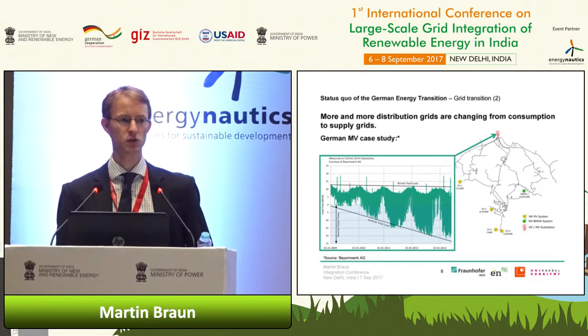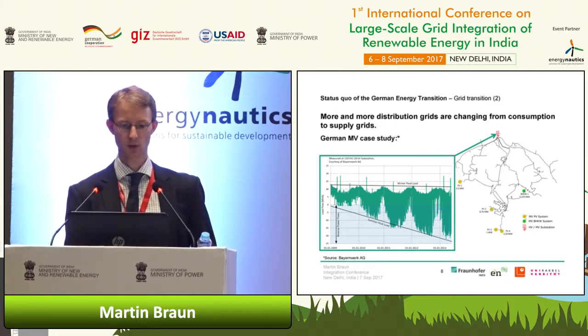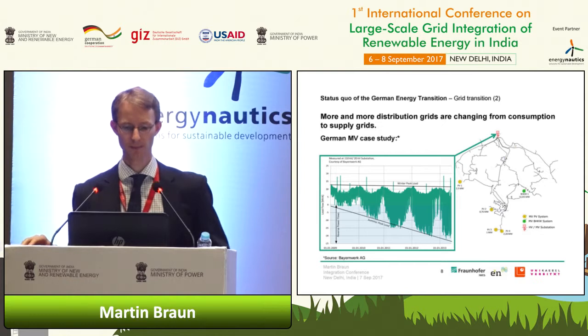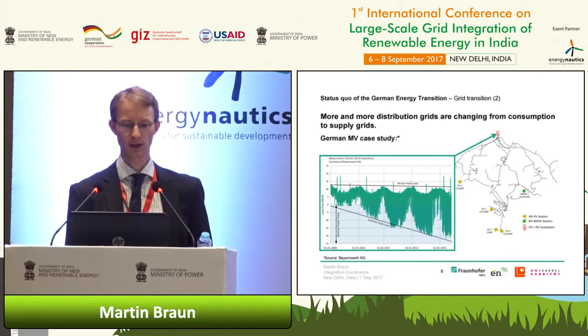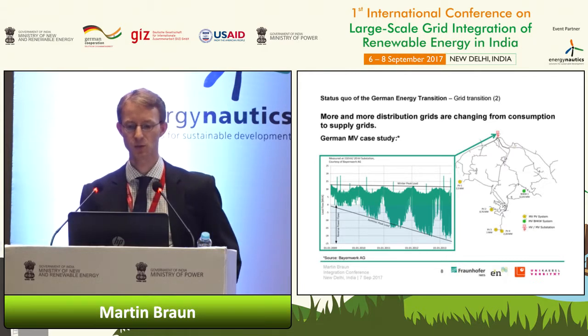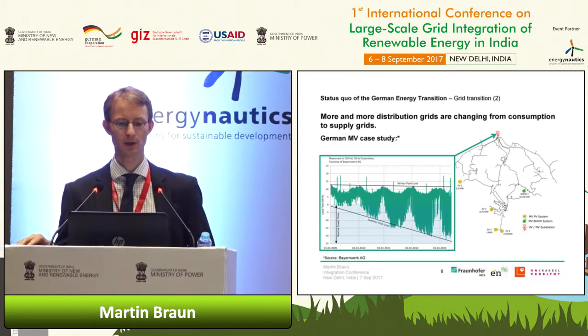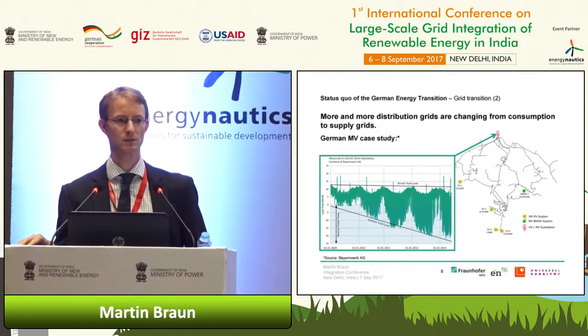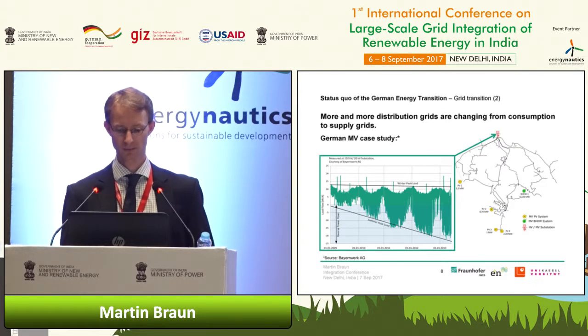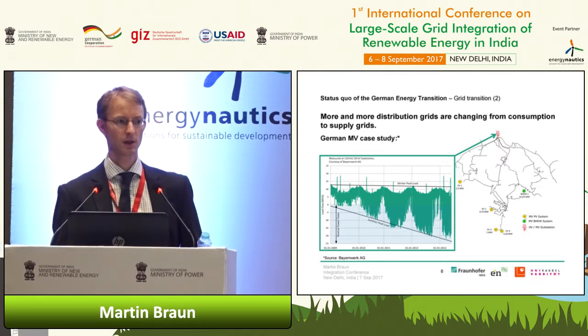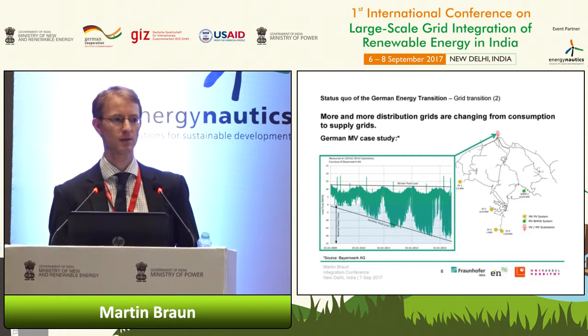This is a high voltage, medium voltage substation in a rural area in Bavaria. You see in 2009 we are in positive values, so it was only consumption nearly. Then we had the very dynamic years of PV production and PV installation enhancements, and within only one year it just extended to negative values—reversal power flows to the high voltage grid, until it doubled in size. So now the dominant factor in sizing the substation is not the load anymore, but the generation.